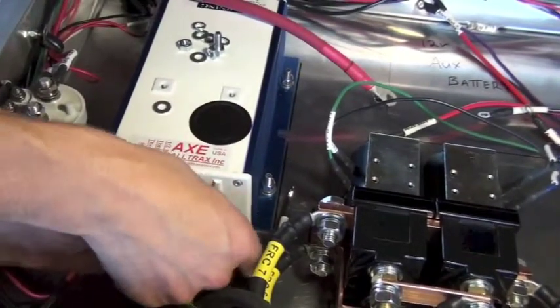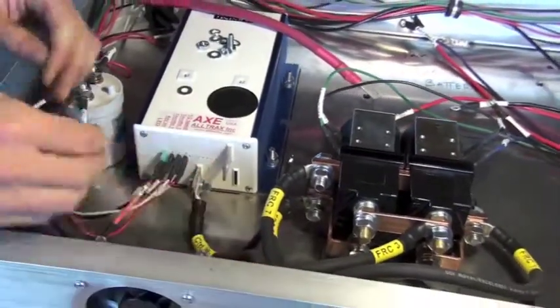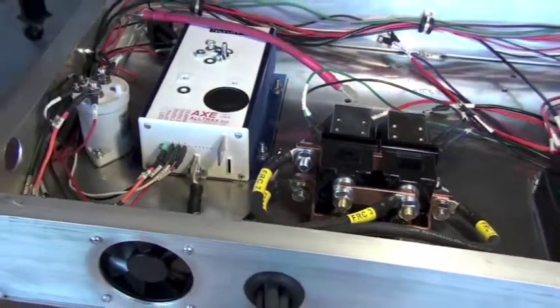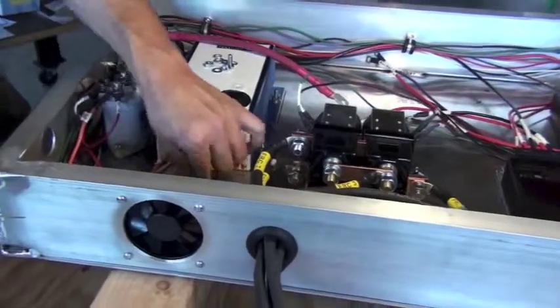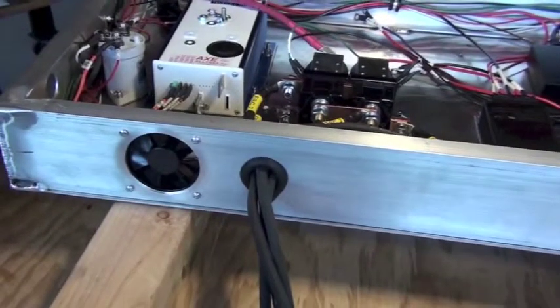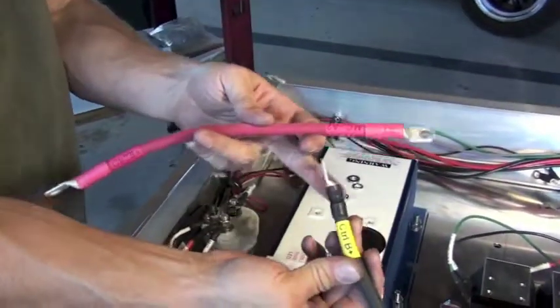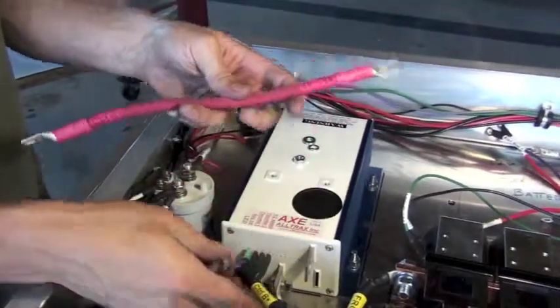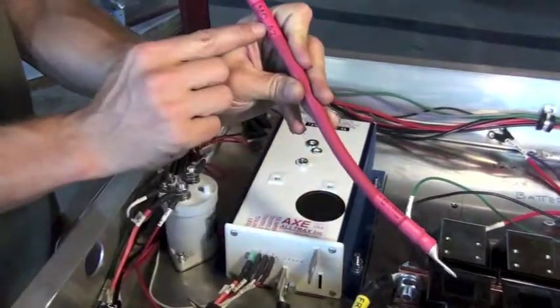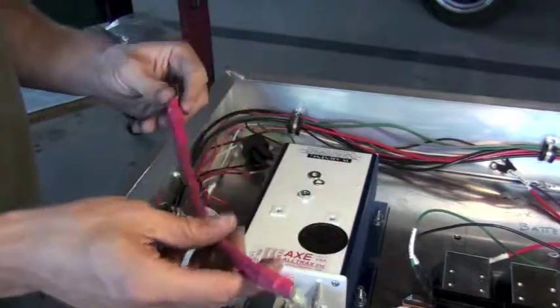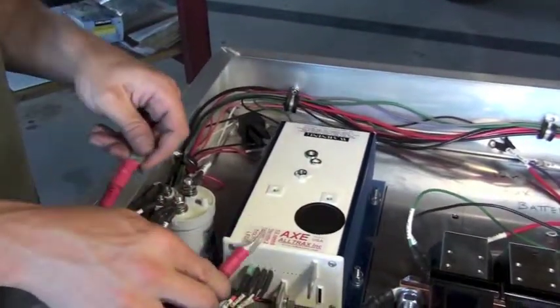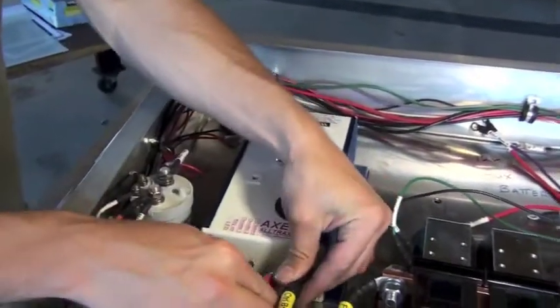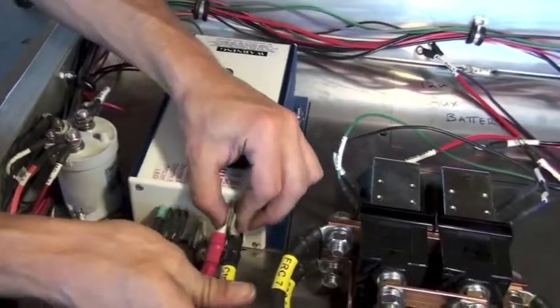And here we can see the correct assembly with our cables spaced properly to reach each termination point efficiently as they enter the high voltage box. We have 2 cables that share the post controller B positive. One is a short red cable and the other is a longer motor cable. We'll put these together on this post on either side of it.